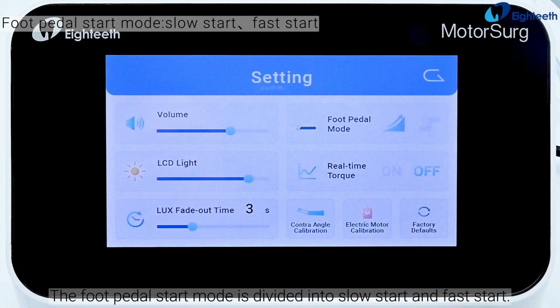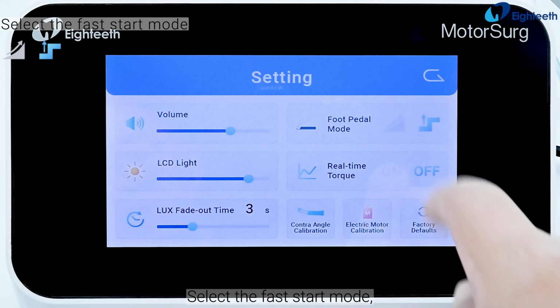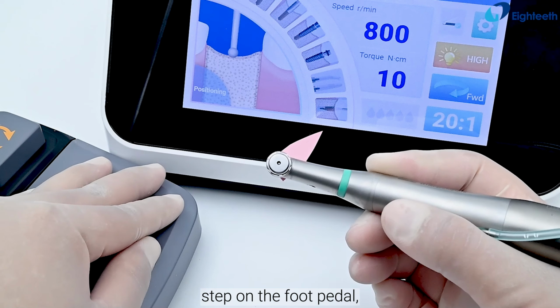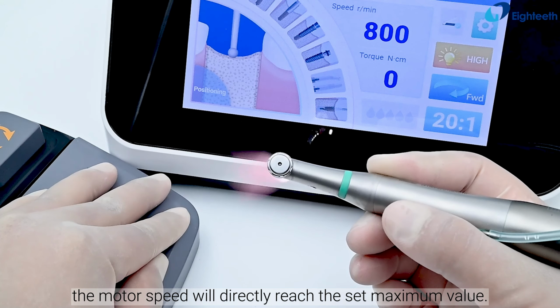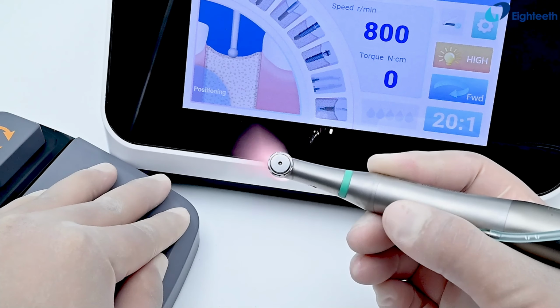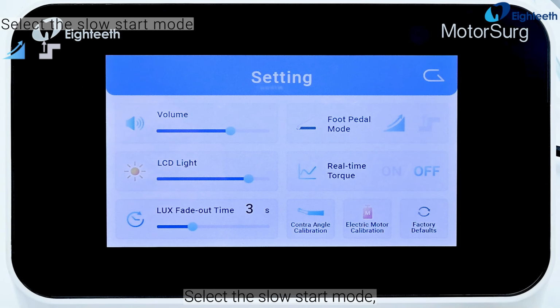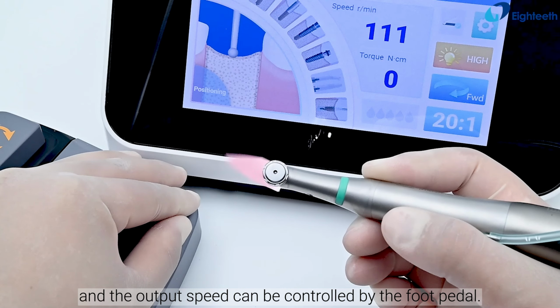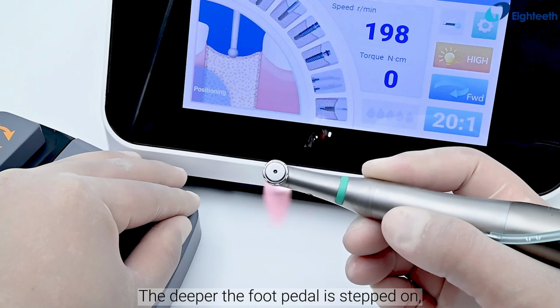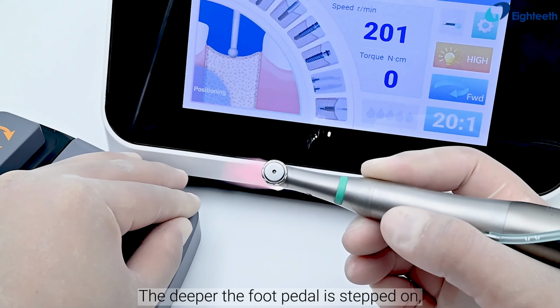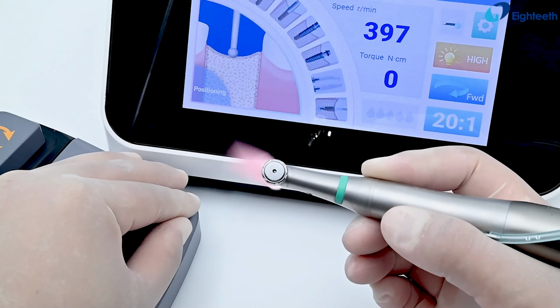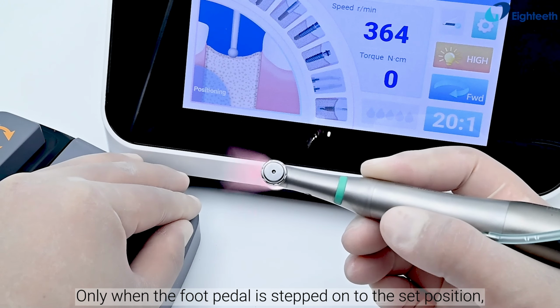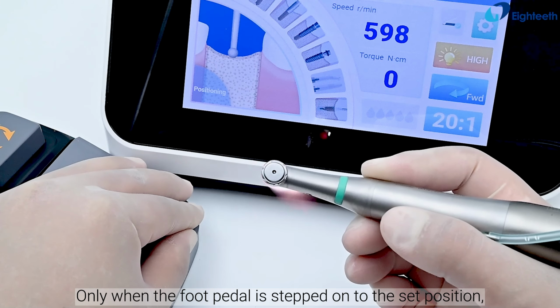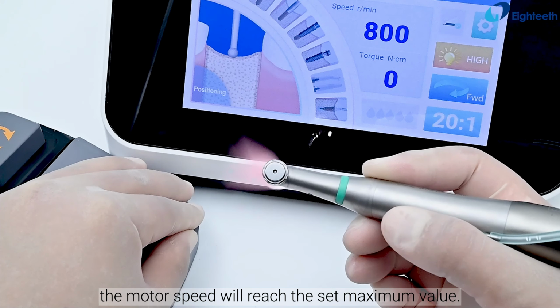The foot pedal start mode is divided into slow start and fast start. Select the fast start mode. Step on the foot pedal, the motor speed will directly reach the set maximum value. Select the slow start mode, and the output speed can be controlled by the foot pedal. The deeper the foot pedal is stepped on, the higher the motor speed will be. Only when the foot pedal is stepped on to the set position, the motor speed will reach the set maximum value.